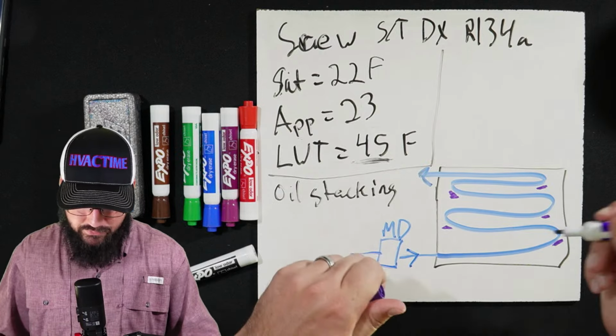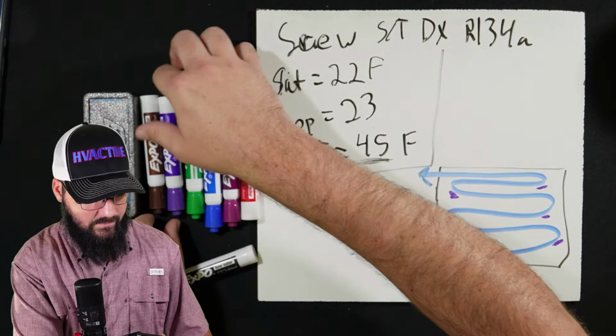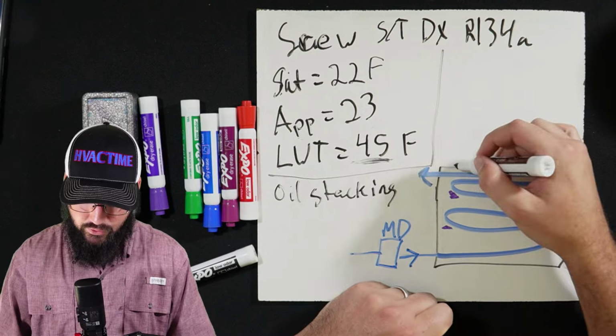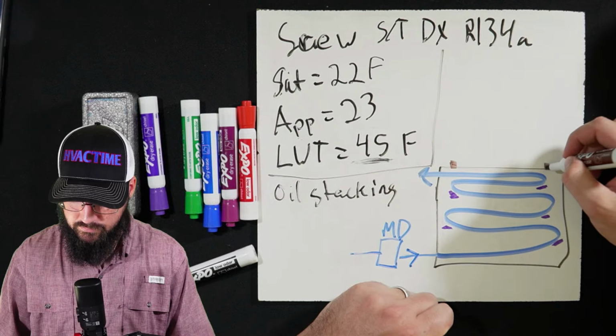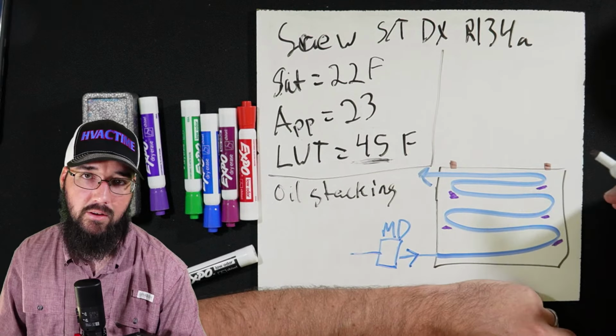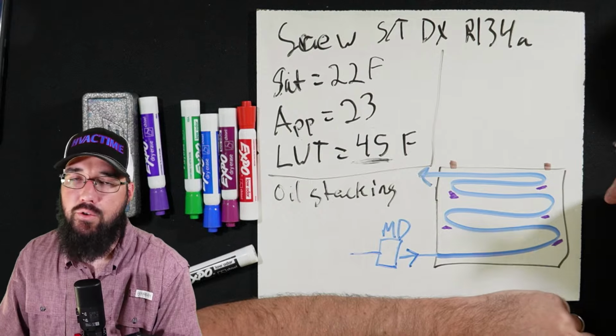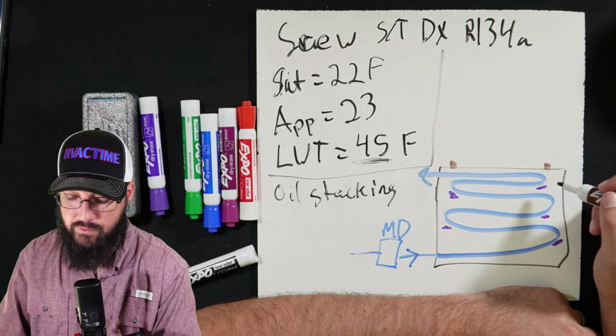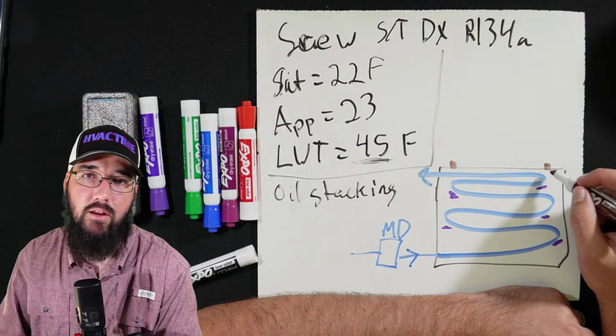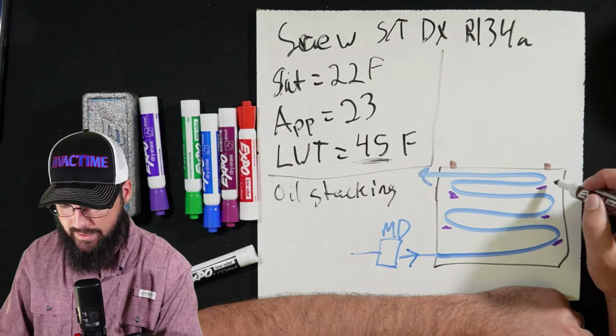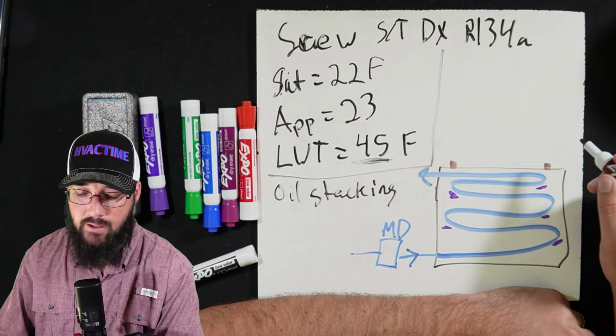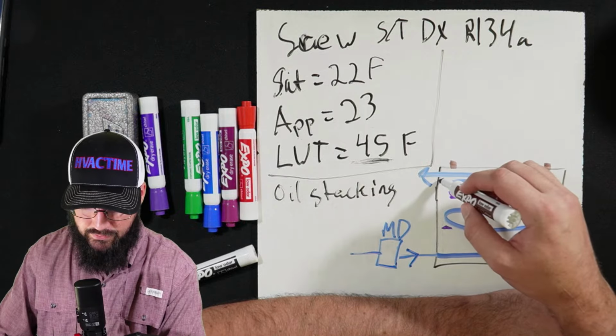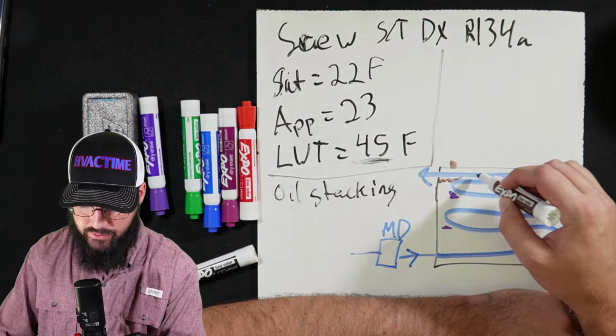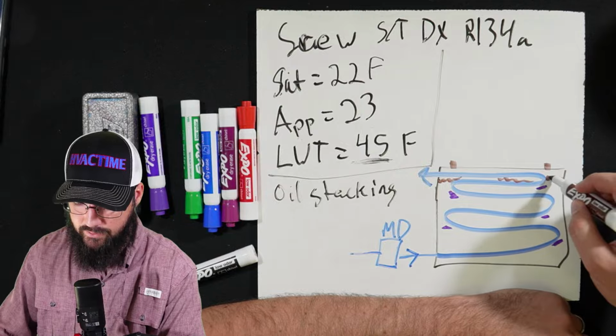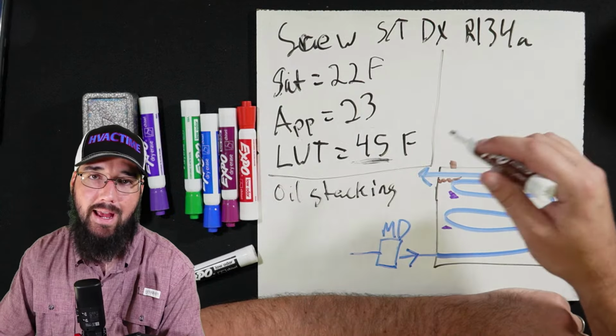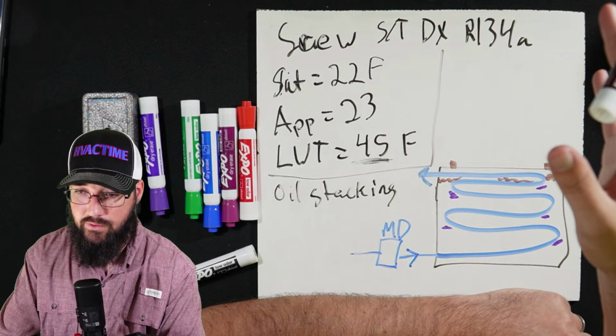So on the top of the evaporator, there's almost always some little taps, right? And they'll usually come from the factory with a plug, right? So it'll be just a threaded plug going into a pressure tap that accesses the water side. What can happen is air can get trapped up in the top of that evaporator, and it won't actually work its way out of the evaporator.